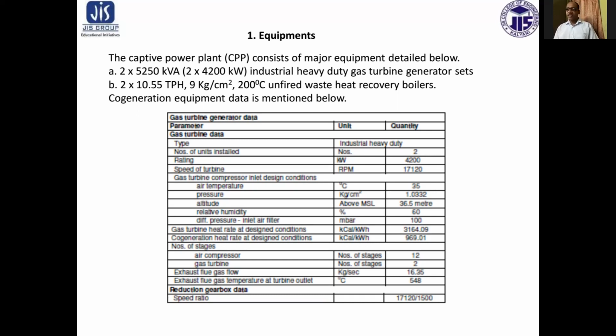Gas turbine heat rate at designed condition is 3164.09 kilocalorie per kilowatt hour, and cogeneration heat rate at designed condition is 969.01 kilocalorie per kilowatt hour. The compressor number of stages is 12, and gas turbine is 2. Exhaust flue gas flow is measured at 16.35 kg per second. Exhaust flue gas temperature at turbine outlet is 548 degrees centigrade. Speed ratio of the gearbox for the generator shaft is 17120 by 1500.